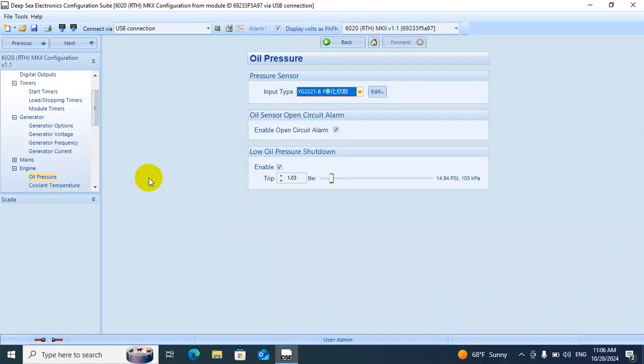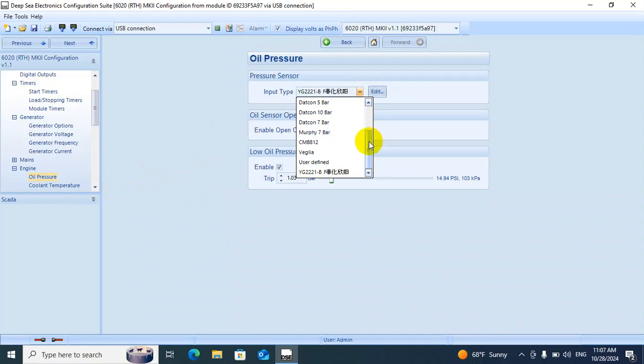Sometimes we don't have the sensor when we are on site, and if we need power, we will come here and make the sensor not used. In this case, we can use the generator without a sensor. The sensor will not show anything, we cannot see anything on the panel, and the panel will not take action because it's not used. But for now, we'll keep it as it is.